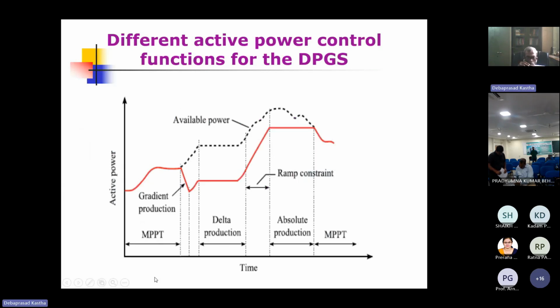Now coming to active power control, most of the time, as I said, the energy available from the renewable sources is variable. Generally, most of these DGs, be it wind or PV, usually follow the maximum power point. But there may be situations where your system cannot absorb the amount of power that is available. At that time, you need to reduce your generation. But please note that whenever you reduce, there are some slopes that you should maintain. You cannot suddenly reduce the generation. It has to be done with a certain slope, which is also specified. And if you want to ramp up, that also has to follow a certain slope. These control features have to be included in the primary control.